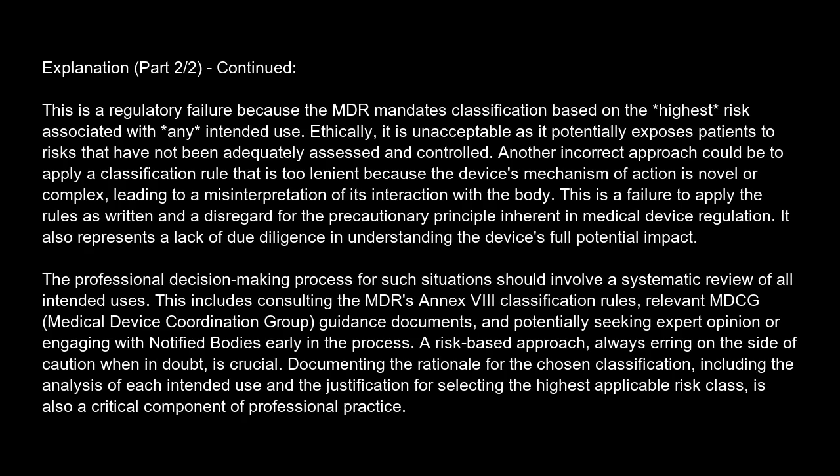The professional decision-making process for such situations should involve a systematic review of all intended uses. This includes consulting the MDR's Annex VIII classification rules, relevant MDCG, Medical Device Coordination Group, guidance documents, and potentially seeking expert opinion or engaging with notified bodies early in the process.